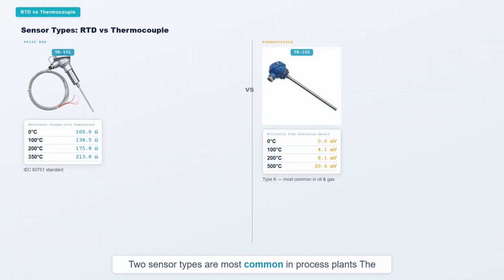Two sensor types are most common in process plants. The PT100 RTD changes resistance predictably with temperature. At 0 degrees Celsius, it reads exactly 100 ohms. At 100 degrees, it reads 138.5 ohms. At 350 degrees, it reads 213.8 ohms. These values follow the IEC 60751 standard. The thermocouple is different. It generates a small millivolt signal from the temperature difference at its junction. A Type K thermocouple produces about 4.1 millivolts at 100 degrees Celsius. You must configure the transmitter to match whichever sensor type is installed.